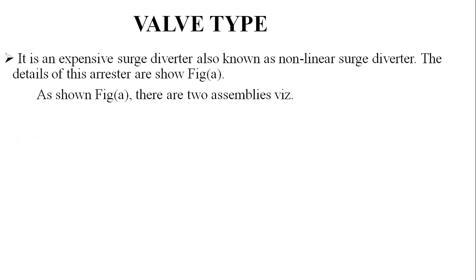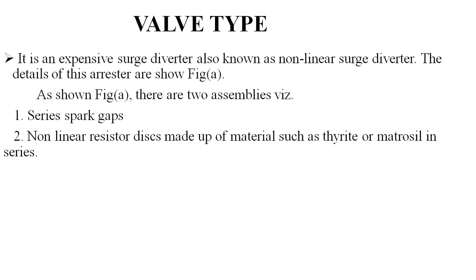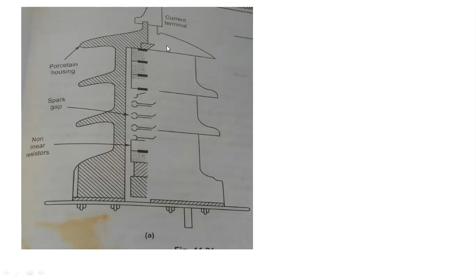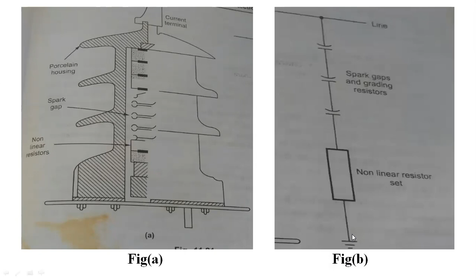Coming to the valve type, it is an expensive surge diverter, also known as a non-linear surge diverter, and the details are shown in this figure, with a series of spark gaps and non-linear resistor discs made up of materials such as thyrite or metrosil in series. Here is our valve. Here are the various spark gaps, porcelain housing, and non-linear resistors with the current terminal over here. This is the non-linear resistor set with a series of spark gaps and grading resistors, which are connected to the line, having a ground to this non-linear resistor set.